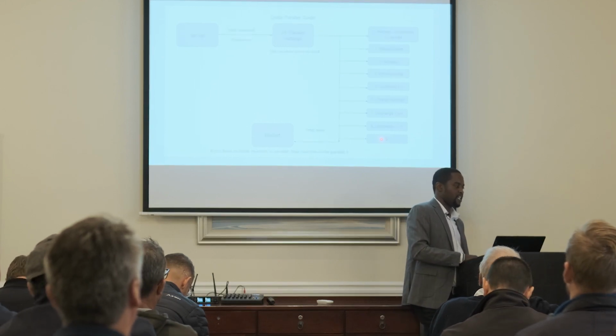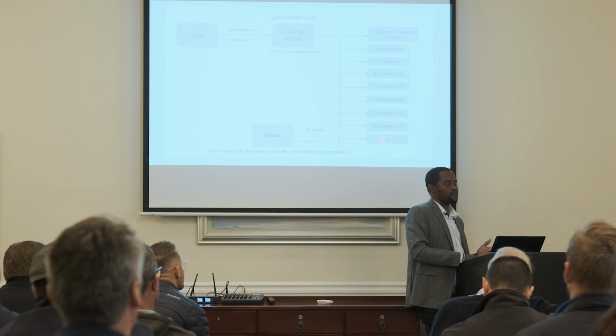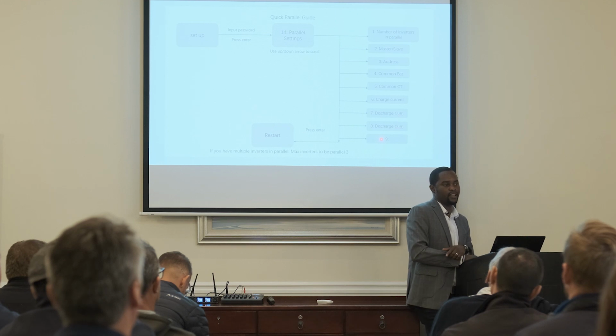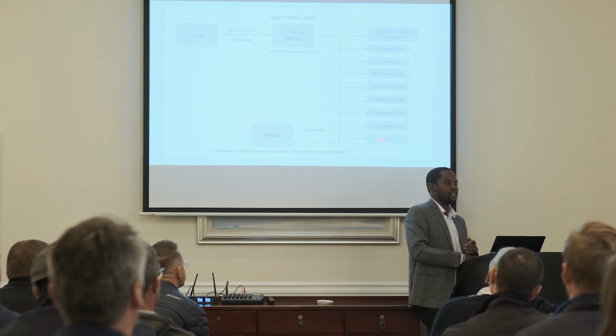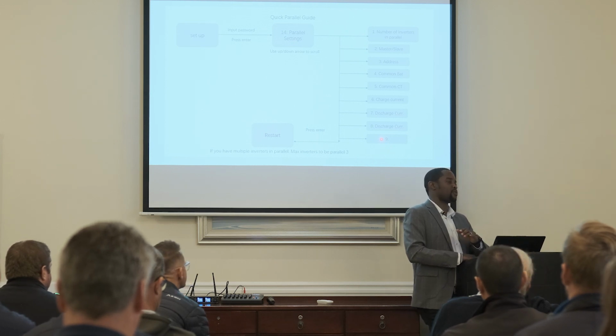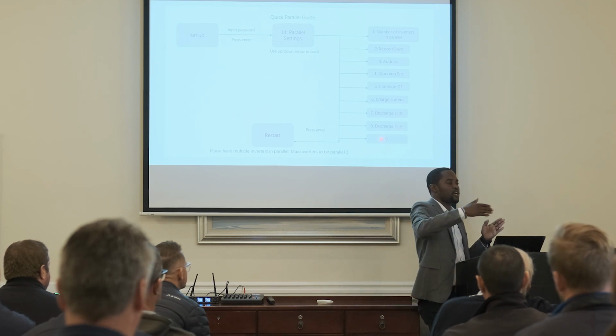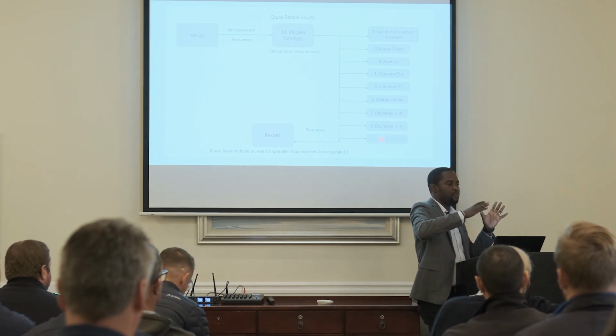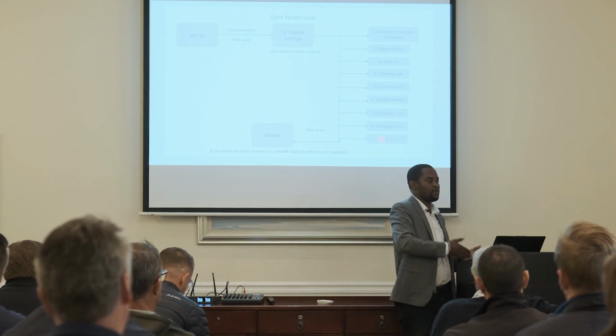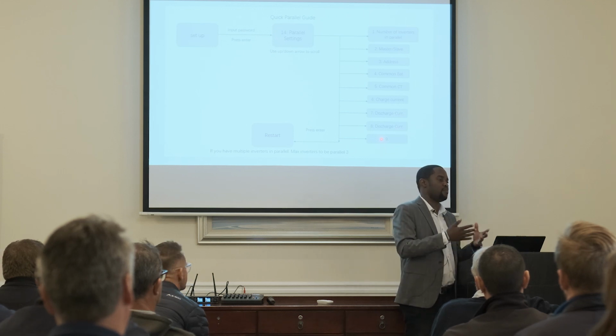So it's also an improvement from what we were having previously, which means with the Samsung, you can actually think that you've got 15 kilowatt hour or 24 kilowatt hour, while at least you only have 16 or 10. You only know when you're on backup and now you can't supply those loads, you are tripping. Or in other cases, all that set point from the CTs is going to the master. The master should actually split the set points and send it to the slaves. So if you lose one of the inverters, all that burden comes to the master. And we've had a few situations where the master is damaged by overload.